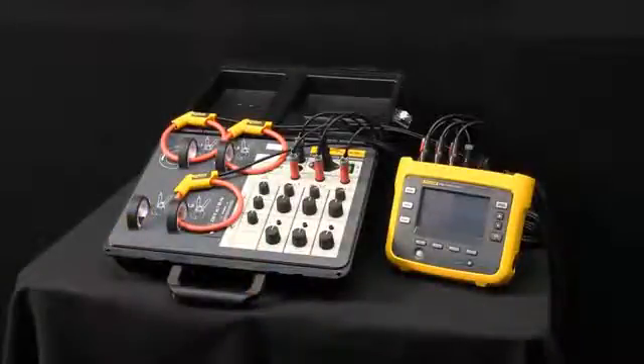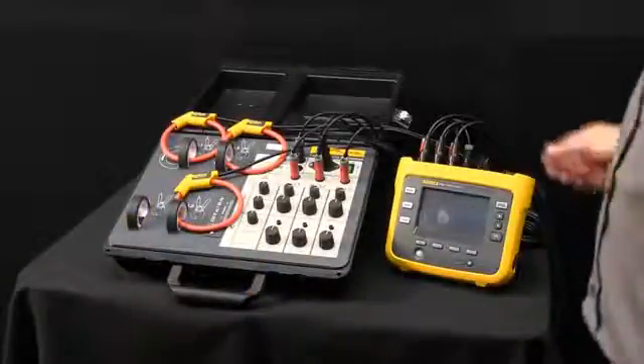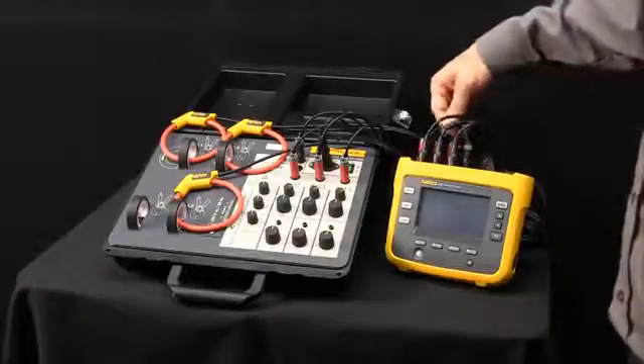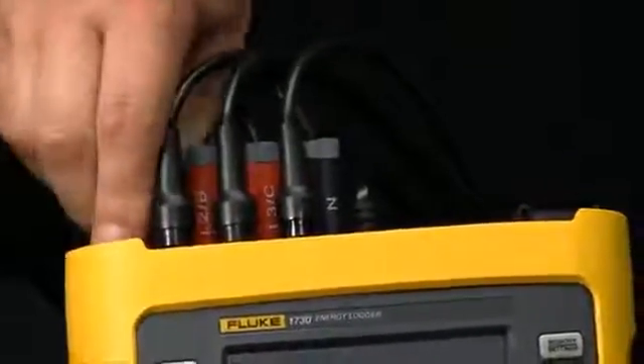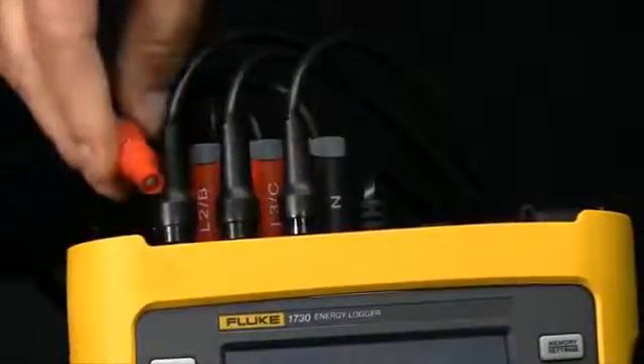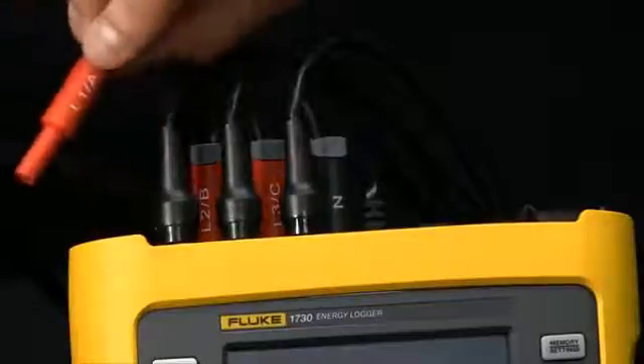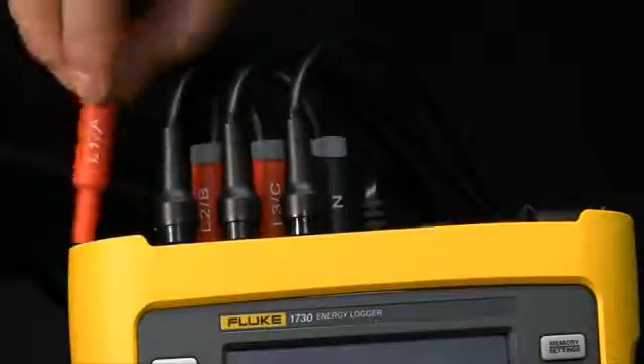Performing a load study with the Fluke 1730 Energy Logger requires connections. Here we've got connections for our voltage. With our voltage connectors we've got a typical 4mm jack. Also has identification on there for which phase it may be on if it's more than one phase.